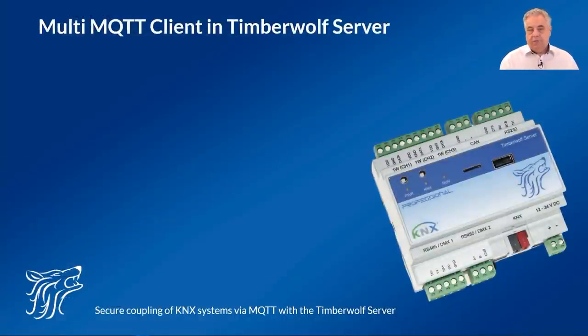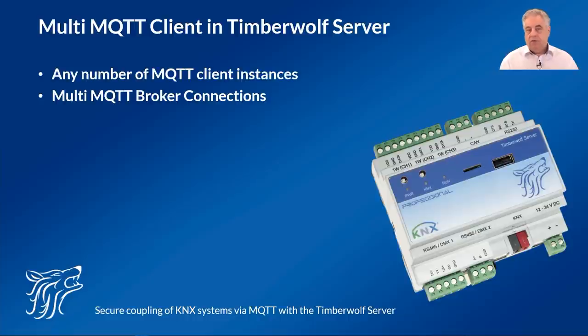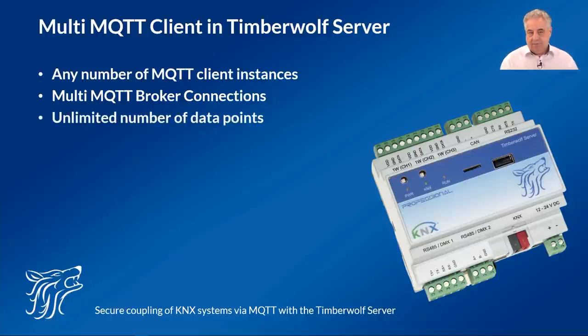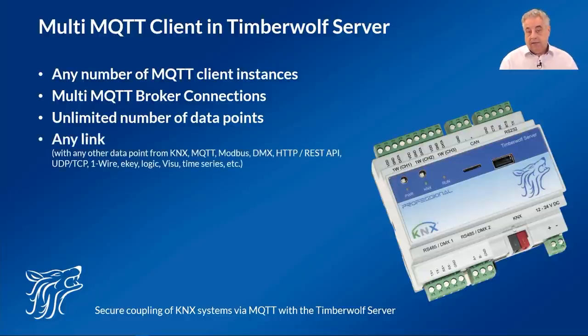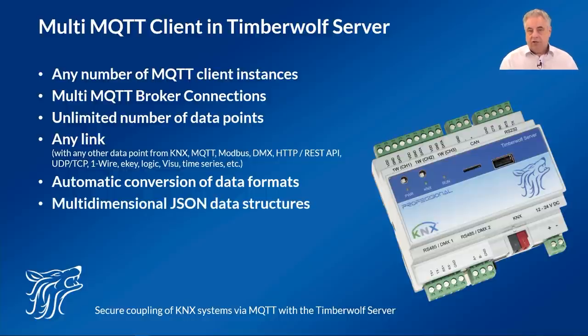The Timberwolf server contains a multi-MQTT client, so any number of instances can be set up. Each MQTT instance can be connected to the same or a different MQTT broker, and this can be changed at any time. There is no limit to the number of data points — you can set up as many as performance allows. All MQTT data points can be linked almost arbitrarily with each other, with data points of other protocols, with logics, visualizations, and for recordings in time series. Data formats are automatically converted if necessary. The MQTT subsystem also supports nested multi-dimensional JSON data structures, meaning extensive data structures can be published or subscribed to and broken down into individual objects during a transaction.